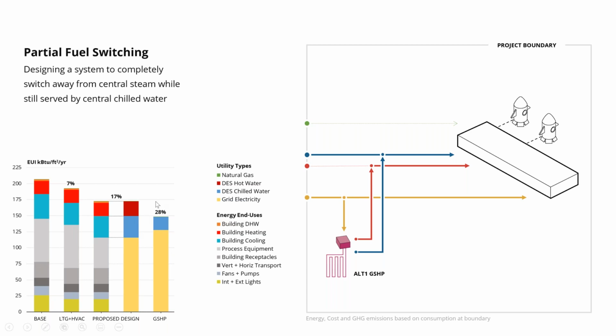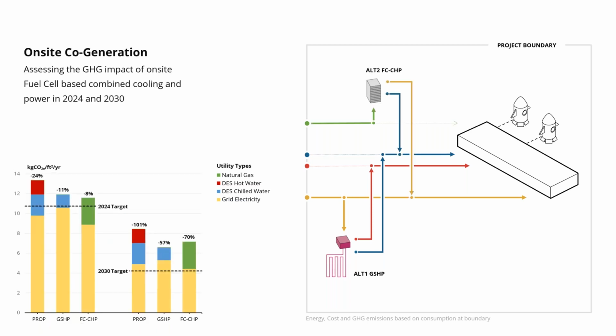Right from the get-go, it's easy to identify that we need to reduce our reliance on the inefficient district energy system. So the next logical step is to consider a cogeneration upgrade. Instead of relying on an inefficient existing trigeneration system for chilled water and hot water, we shift to a more efficient cogeneration facility. This gets us closer to our 2024 Local Law 97 targets, but we're nowhere near our 2030 targets. There's an underlying assumption that as the grid gets cleaner, the electricity associated with the project gets cleaner. But switching to on-site cogeneration doesn't really help, because natural gas doesn't change over the course of 10 years. So the reliance on natural gas kind of weighs us down.